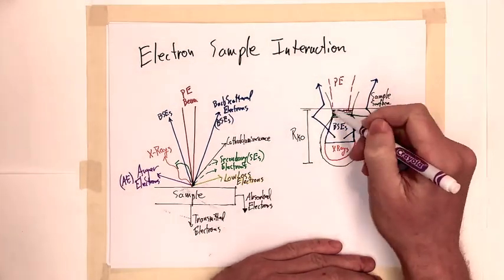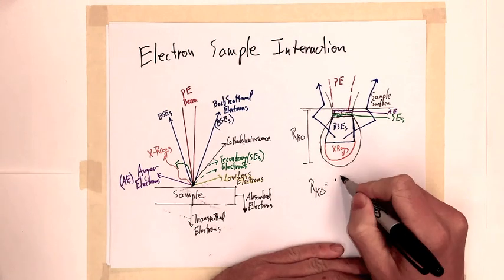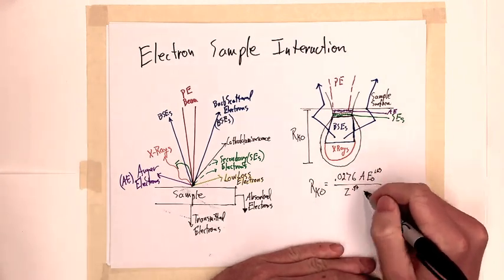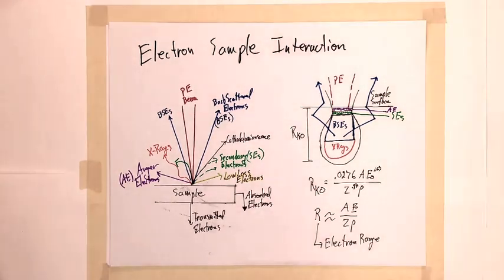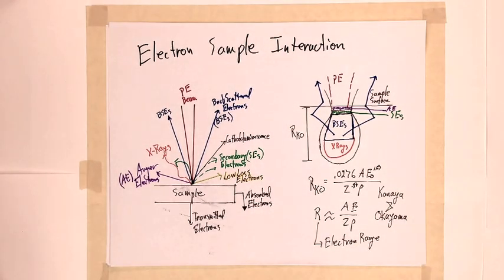Backscattered electrons tend to lose more energy as they propagate further into the sample. So the maximum usable information depth of backscattered electrons is often on the order of half of the total electron range.